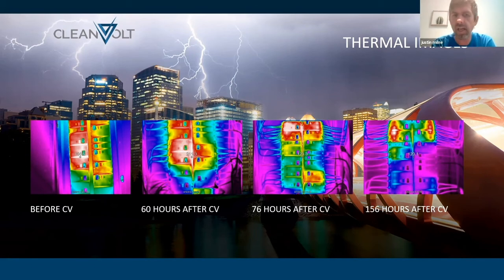This picture was taken 60 hours later by the customer, and we found it interesting that the heat was migrating. Up to this point, when these thermal images were done in 2014, we had been provided lots of feedback verbally over the phone or letters from customers reporting that they noticed a difference in heat on their systems. But this was the first time we had actually visually seen it provided to us by a customer. As you can see, 76 hours later, the heat dynamic on the load center has changed significantly. And the breaker that the CleanVolt is installed on in the bottom right-hand side in the 76-hour after picture is now hot and showing as heat on the thermal image.